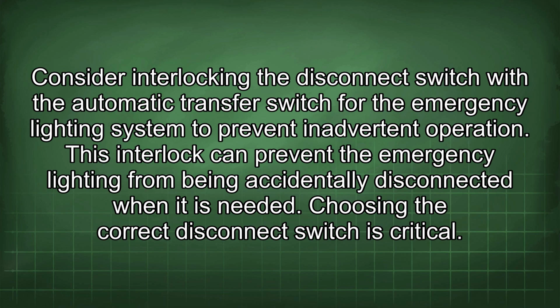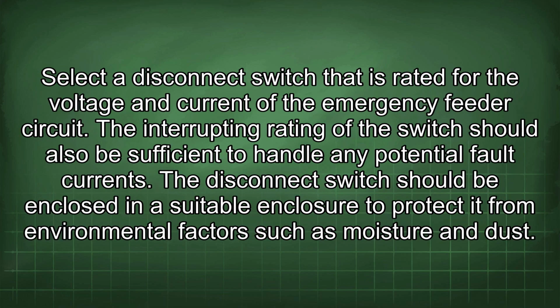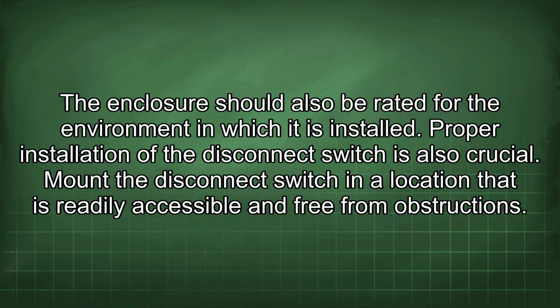Choosing the correct disconnect switch is critical. Select a disconnect switch that is rated for the voltage and current of the emergency feeder circuit. The interrupting rating of the switch should also be sufficient to handle any potential fault currents. The disconnect switch should be enclosed in a suitable enclosure to protect it from environmental factors such as moisture and dust. The enclosure should also be rated for the environment in which it is installed.